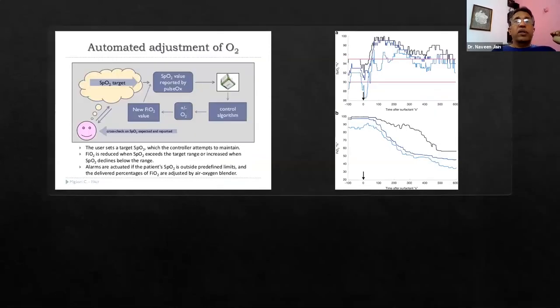Even smarter use of computers is now happening. You can have an arterial line running from the baby and being fed to the computer. Dial in and say 'I do not want a PO2 of more than 70.' If the PO2 of the baby goes more than 70, automatically it will reduce the FiO2 in the ventilator. So you can reduce the rate of ROP and hyperoxy-related injuries. This is already available in clinical practice.